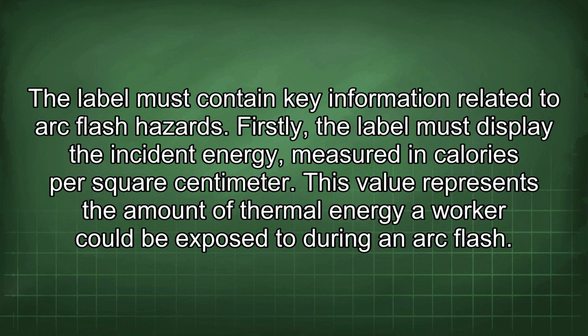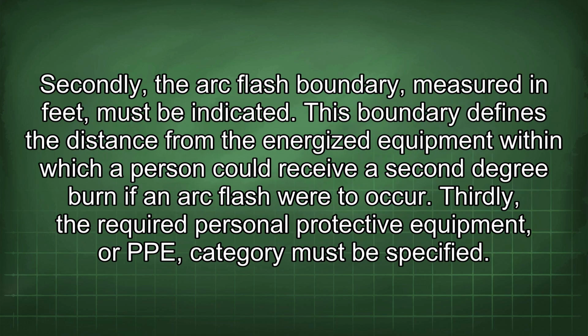The label must contain key information related to arc flash hazards. Firstly, the label must display the incident energy, measured in calories per square centimeter. This value represents the amount of thermal energy a worker could be exposed to during an arc flash. Secondly, the arc flash boundary, measured in feet, must be indicated. This boundary defines the distance from the energized equipment within which a person could receive a second-degree burn if an arc flash were to occur.